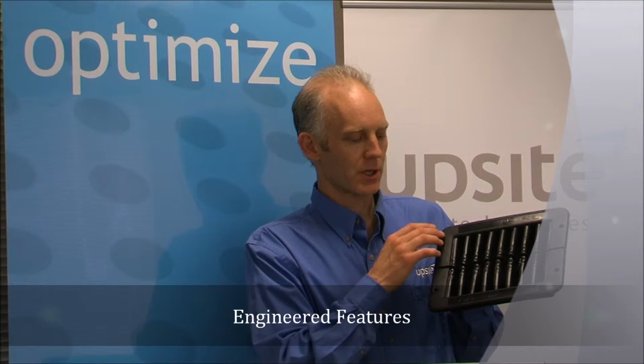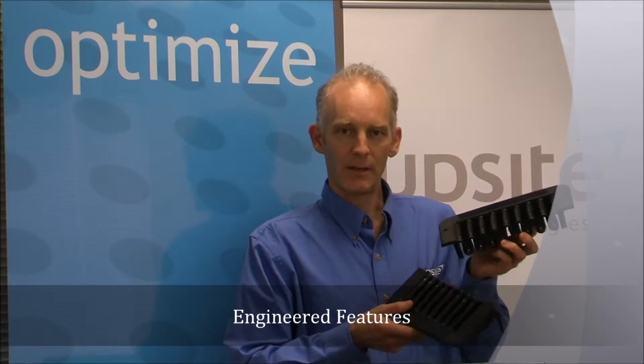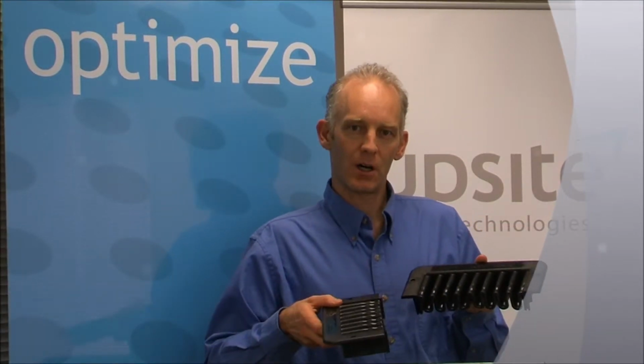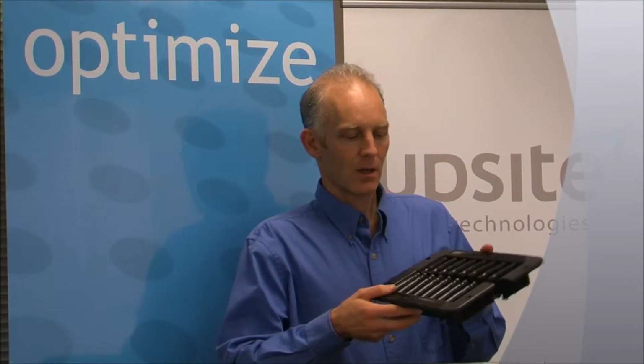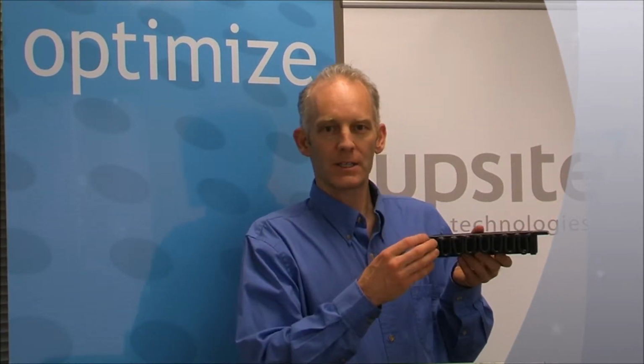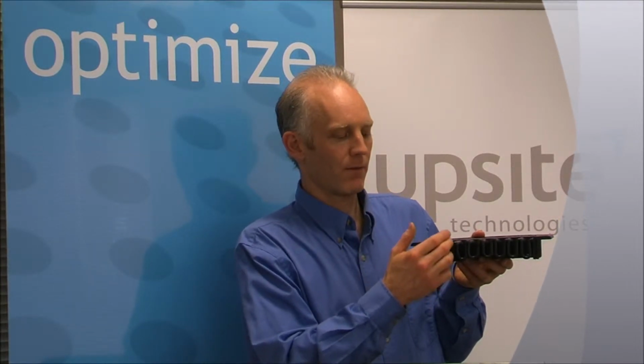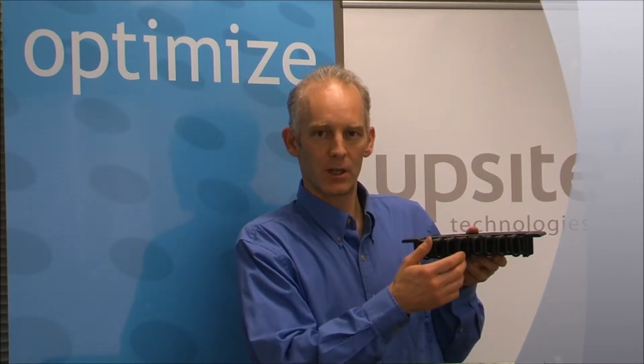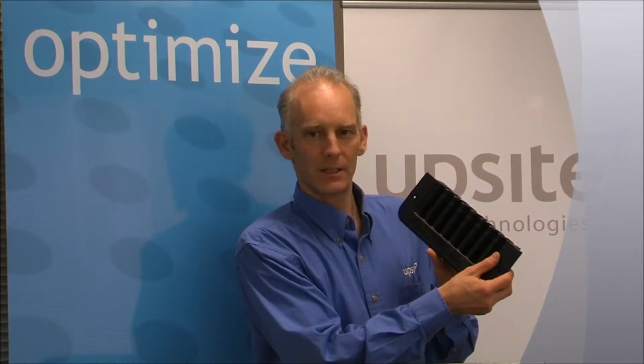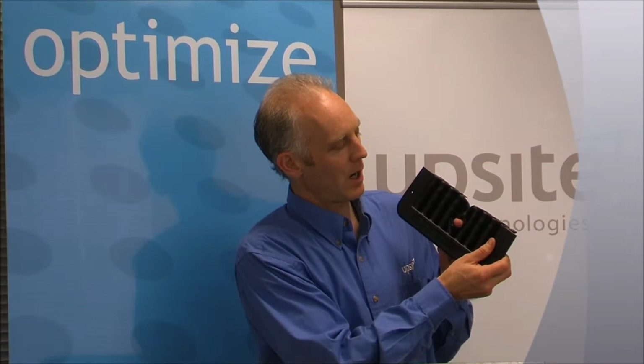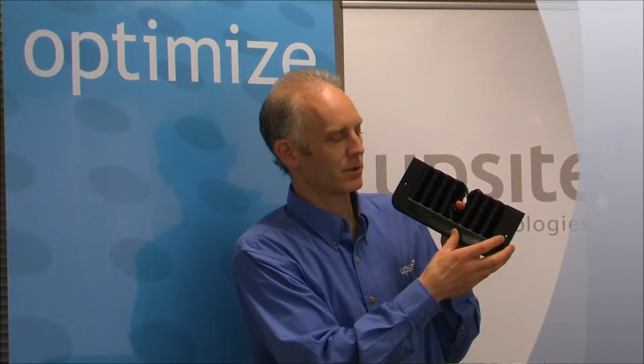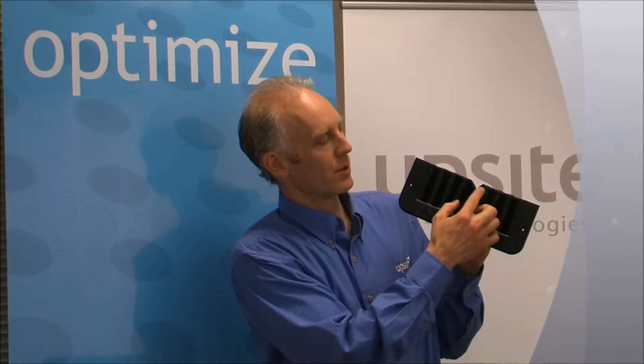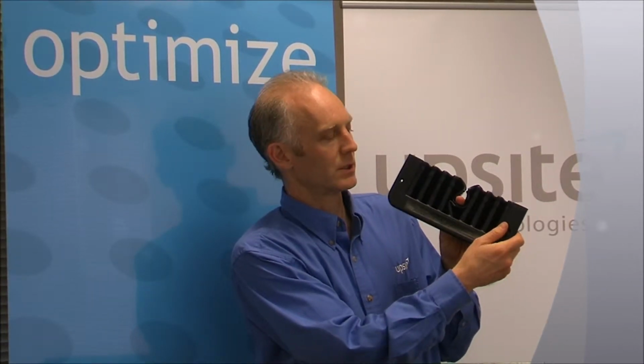I'll now talk to you about the features of the KoldLok Wave and the engineering that's gone into this product. First, it's constructed with an ABS frame and a thermoplastic elastomer. It's split so that it can be installed around existing cabling. Now looking at a cross-section of the elastomer, you can see the wave form. This creates a lot of extra surface area. One of the benefits of this is that when penetrants are pulled off of the center, which invariably happens as cables run through a cable opening, the elastomer wraps back around and seals the opening.